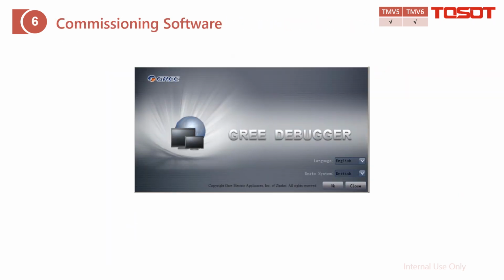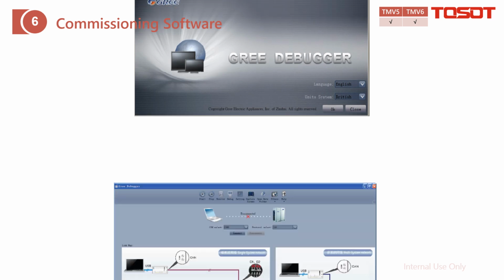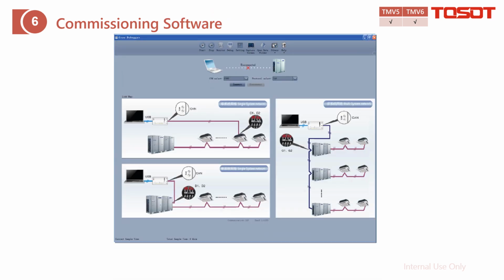And here is the interface. From here, you can select the language and also the unit. And for the detail, you can also go to my other GMV PC debugger video. Here is just the summary. And from here, you can connect to the PC. This is the GMV system for a single unit. And for a single system, you can connect to the indoor unit or to the outdoor unit D1, D2, which is okay. But for the multi-system, only from the master outdoor unit G1, G2 from the LV system.